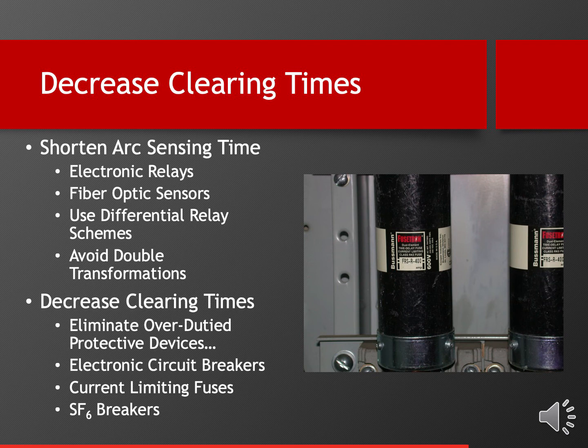Fiber optic sensors, if you're having trouble finding overcurrent settings that coordinate for you engineer types, fiber optic sensors work great because they don't need coordination to work. They actually sense an arc flash. They sense a flash event and a preset amount of current flow. It has a Boolean AND gate between them for you engineering types. And if it sees a flash of light and a preset amount of current, it interprets that as a fault, and it will clear the system pretty much instantaneously. Using differential relays, it's like a GFCI kind of a system, but a differential relay compares incoming and outgoing current flow. And again, for protecting things like transformers or buses, they're particularly fast. And the faster they are, of course, the better it is from incident energy.